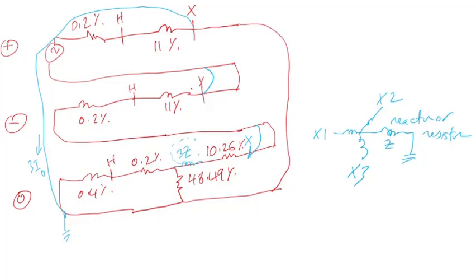Hello and welcome to Engineering Simple. In the previous video I talked about the objectives of this video series: calculating the line-to-ground fault, then trying to limit the fault current to a certain limit. We can do that by adding a neutral grounding resistor or a neutral grounding reactor to the neutral of the low voltage windings. This is where I left off — I started drawing the sequence networks.